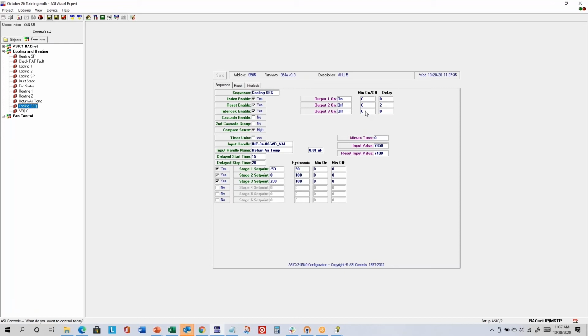And notice the min on off will count from 1 and 0. There is a minimum value of 1 for the min on off. So if you're in minutes, that's more substantial, more significant than when it's 1 second, because when it turns on, it will stay on for at least a minute. So then they all gracefully staged up.